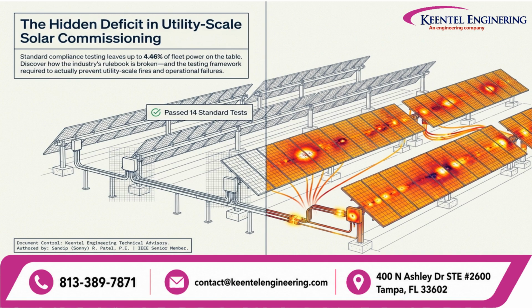Welcome, everyone. In utility-scale solar, there is a dangerous assumption that passing conventional handover testing means a plant is healthy. The reality is stark. Standard compliance testing leaves up to 4.46% of fleet capacity completely unaccounted for on day one. On paper, arrays pass all 14 standard checklist tests. In reality, undetected contact resistance, cell microcracks, and insulation faults are already generating invisible hotspots and laying the groundwork for catastrophic fires. Today, we're breaking down why the traditional commissioning rulebook is broken and outlining the technical testing framework required to ensure true asset safety and performance.